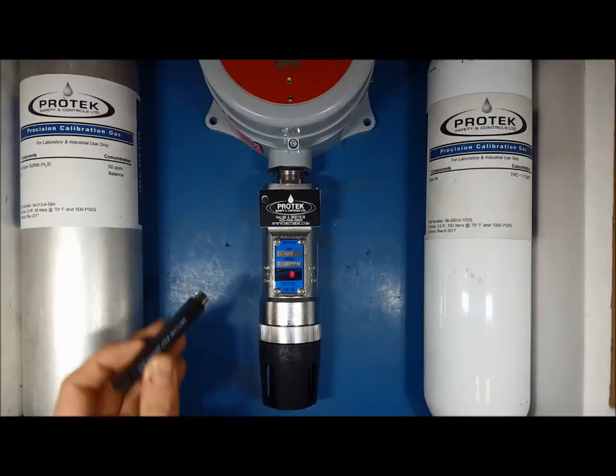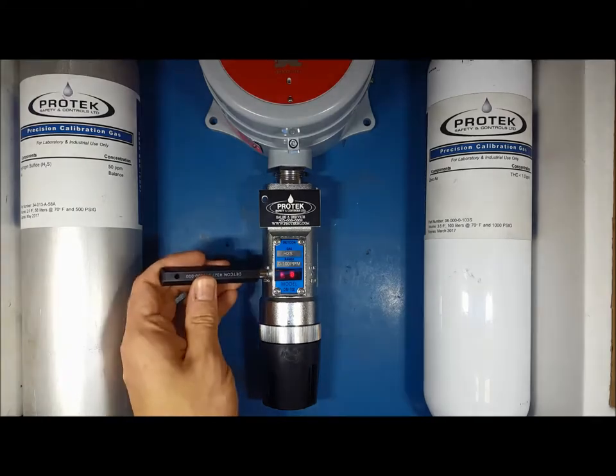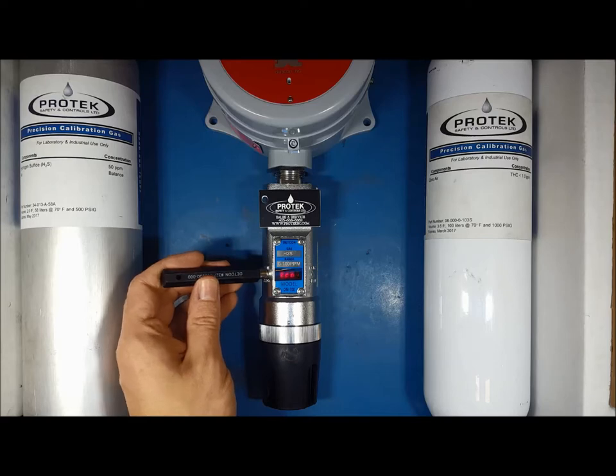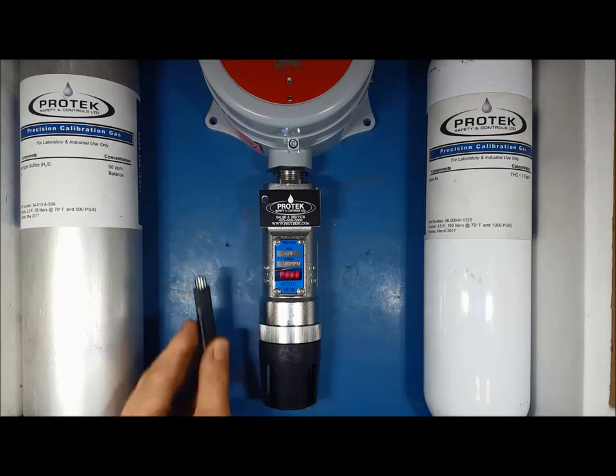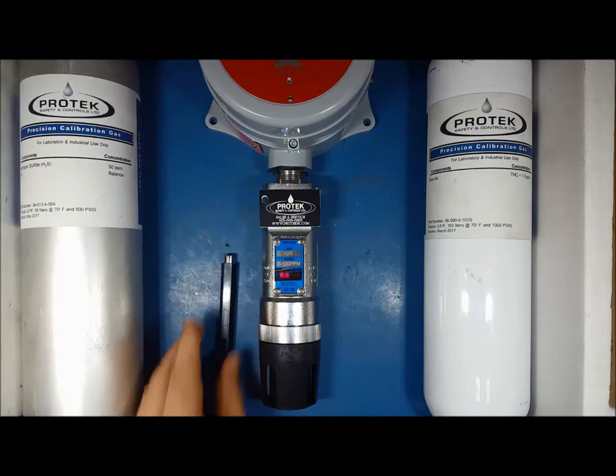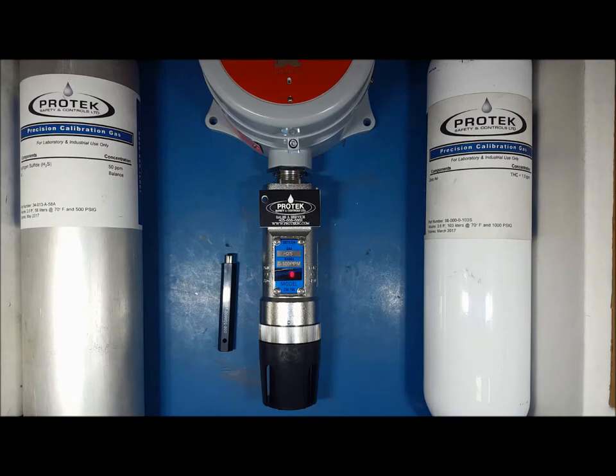Using the magnet that is supplied with the unit, hold it above the icon PGM1 at the transmitter. An arrow will appear on the display indicating that you are interacting with the transmitter. The arrow will be pointing left, indicating that you are selecting PGM1. After a few seconds, the operational display will change to the calibration menu, which will display PGM1 equals 0 and PGM2 equals span, going across the screen. If you do not hold your magnet over either PGM1 or PGM2, the calibration menu will go back to the operational display in operational mode after 2 cycles of the calibration menu.